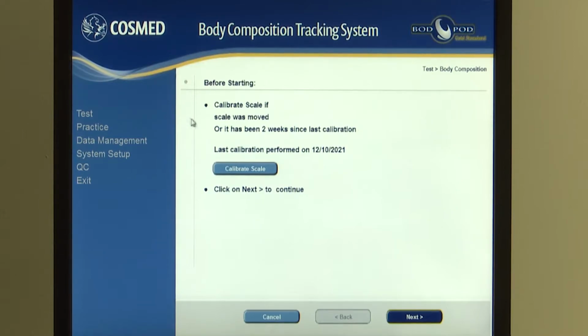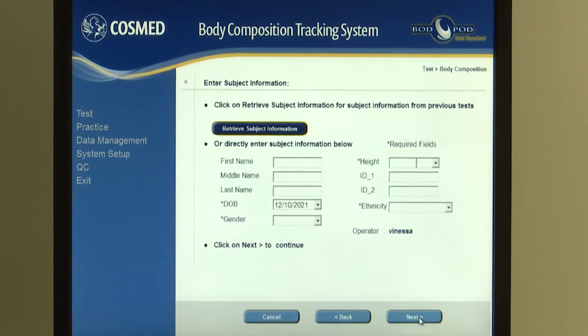The software will ask to confirm if the scale calibration has been done within the past 2 weeks. If it had not been completed, the Calibrate Scale tab will need to be clicked, and the entire scale calibration will need to be completed. For this demonstration, it has been completed, so the Next tab can be clicked.